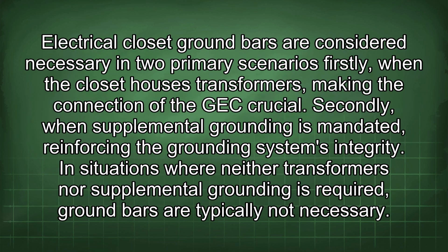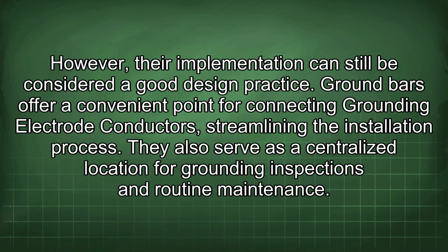Electrical closet ground bars are considered necessary in 2 primary scenarios. Firstly, when the closet houses transformers, making the connection of the GEC crucial. Secondly, when supplemental grounding is mandated, reinforcing the grounding system's integrity. In situations where neither transformers nor supplemental grounding is required, ground bars are typically not necessary. However, their implementation can still be considered a good design practice.